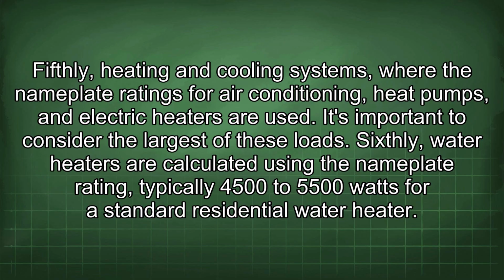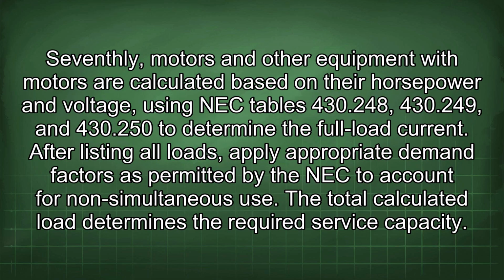Fifthly, heating and cooling systems, with the nameplate ratings for air conditioning, heat pumps, and electric heaters are used. It's important to consider the largest of these loads. Sixthly, water heaters are calculated using the nameplate rating, typically 4,500 to 5,500 watts for a standard residential water heater. Seventhly, motors and other equipment with motors are calculated based on their horsepower and voltage, using NEC tables 430.248, 430.249, and 430.250 to determine the full load current.